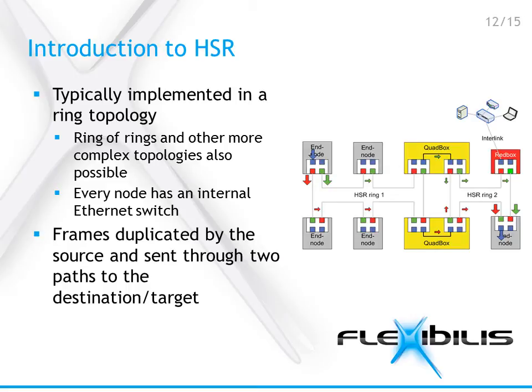In HSR, the source node duplicates the frames and sends them to the destination using two different paths, as you can see in the picture. Even if one node or link breaks down, the packet still reaches the destination the other way.